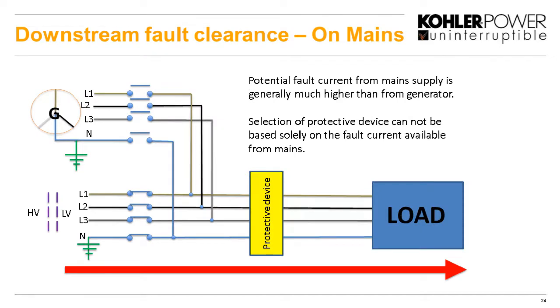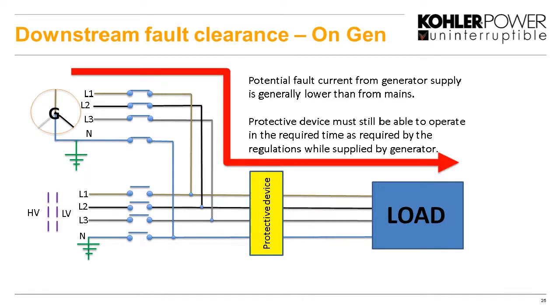So look at this little quick diagram here. We have the mains running as normal, and we have a protective device protecting the load for any downstream faults. And we can understand that the potential fault current from the mains is typically and generally much higher than it is from a generator. So we can't solely use the actual potential fault current from the transformer to select the protective device, because when it's running on generator, we then have a different potential fault current, and this might possibly have to be the parameters that we use to select that protective device. So also when we're looking at putting a generator in, will all the protected devices still operate correctly with the design and capabilities of the generators that you're putting in? Okay, so it's an important consideration to look at.